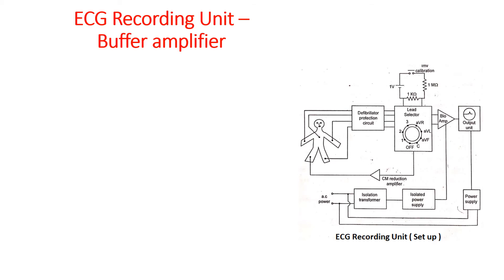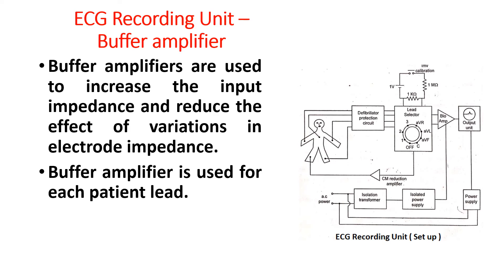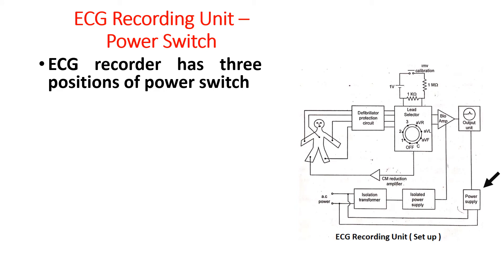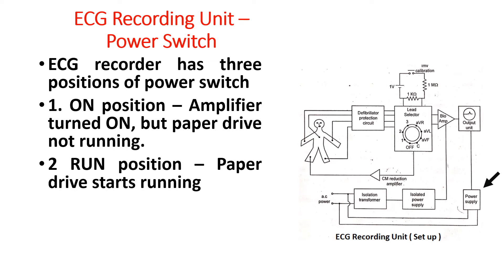Buffer amplifiers are used to increase the input impedance and reduce the effect of variations in electrode impedance. A buffer amplifier is used for each patient lead. The ECG recorder has three positions of the power switch. First is the on position — amplifier is turned on but the paper drive is not running. Second is the run position — paper drive starts running. The third position is the off position — ECG unit is switched off.